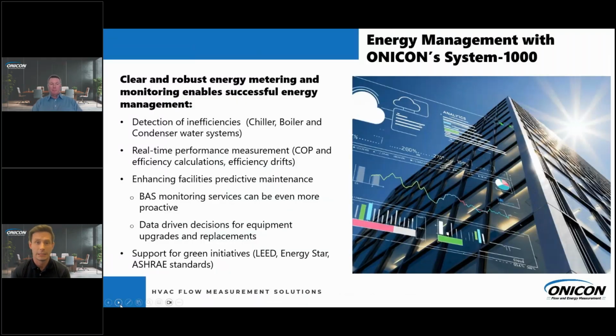And to have successful energy management, we need to have a clear and robust energy metering or energy monitoring plan so we can detect energy inefficiencies when they're occurring, such as a chiller system, a boiler system, a condenser water system. By installing a System 1000, you can see that data immediately in real time. We can calculate COP, energy efficiency calculations, and energy drifts. Now, if you remember when Scott was talking about his applications, if you remember the boiler diagram, let's assume that you have a high condensing boiler that is near 100% efficient. You want to ensure that boiler is operating at its peak efficiency. If not, it's costing you money.